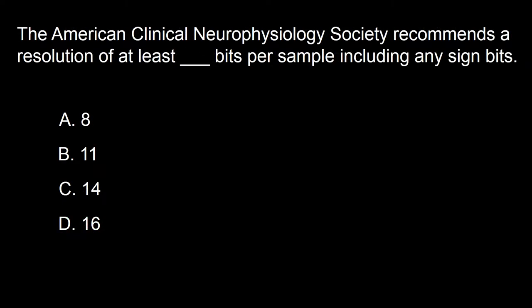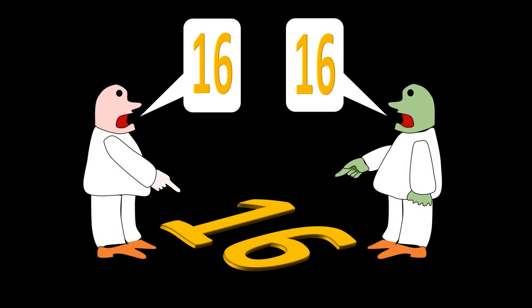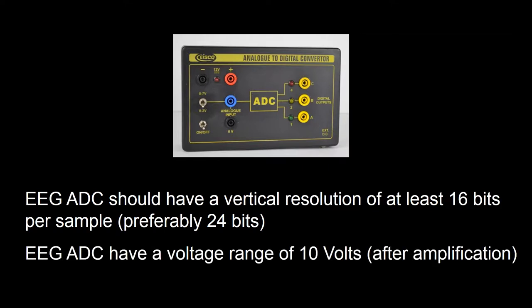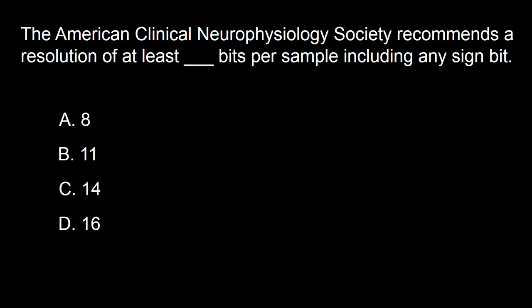Next question: the American Clinical Neurophysiology Society recommends a resolution of at least dash bits per sample including any sign bits. A: 8, B: 11, C: 14, D: 16. The recommended number of bits per sample is 16. EEG analog-to-digital converters should have vertical resolution of at least 16 bits per sample, preferably 24 bits per sample. EEG analog-to-digital converters have a voltage range of about 10 volts after amplification. The answer is D.